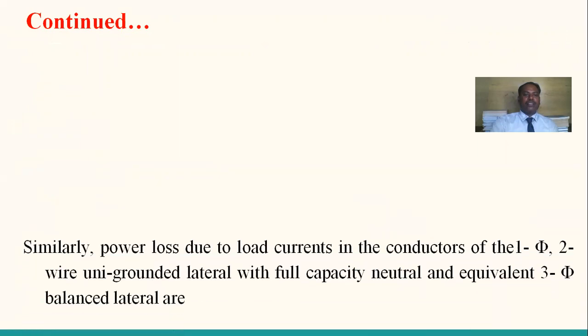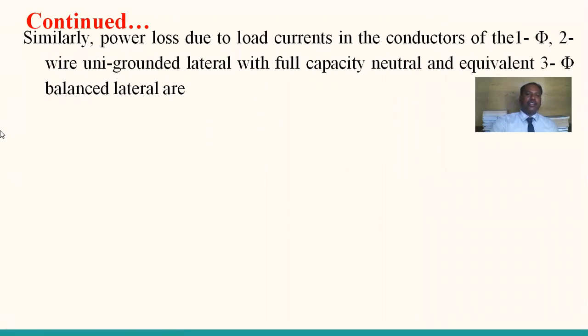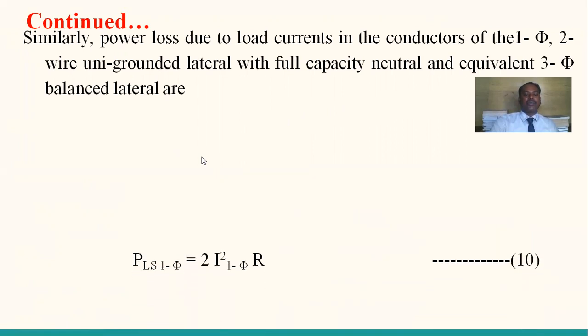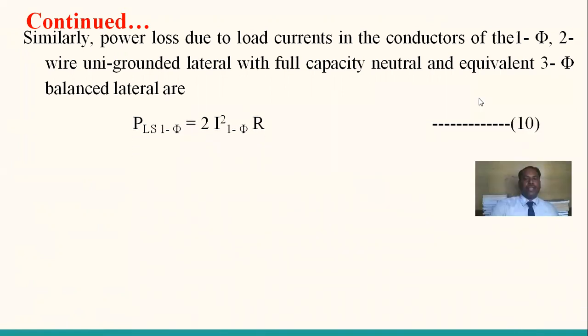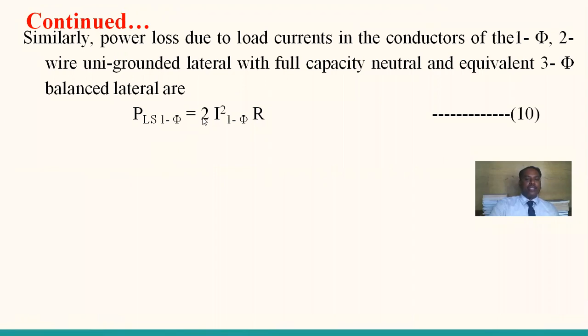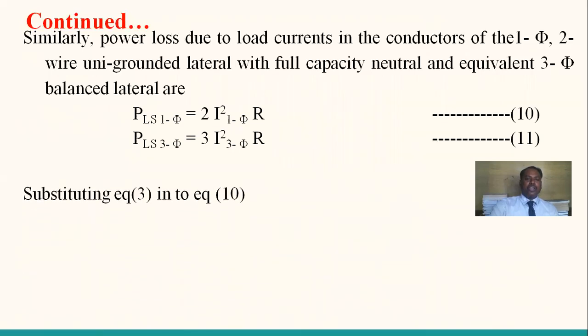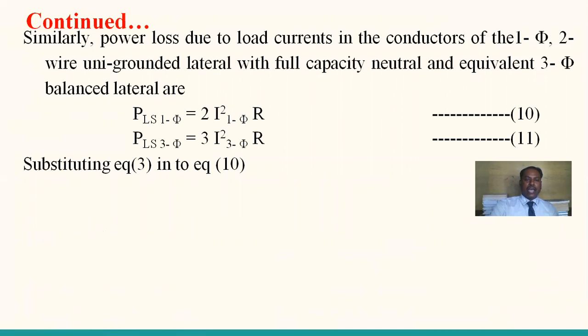And similarly, we can concentrate on the power loss calculation. Similarly, power loss due to load currents in the conductors of the single phase 2-wire uni-grounded lateral with full capacity neutral and the equivalent 3-phase balanced lateral are, see, the power loss of a single phase lateral, it is 2 conductors, 2 I square single phase into R, and it is 3 conductors, 3 I3 phase square into R, and substituting equation 3 in equation 10, equation 3 is I single phase is equal to 3 times I3 phase.